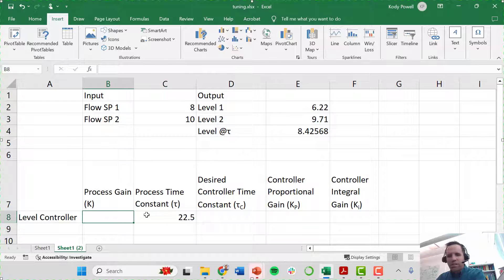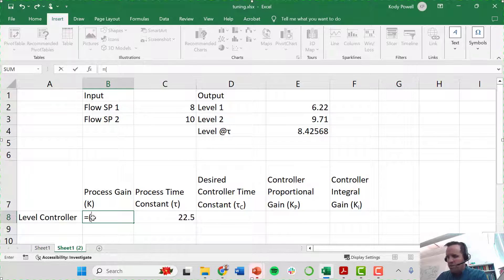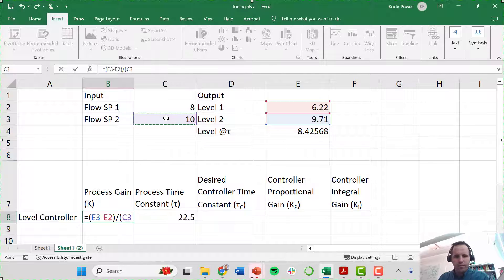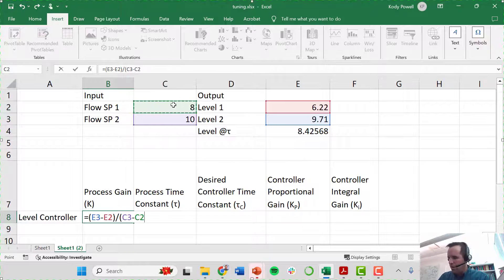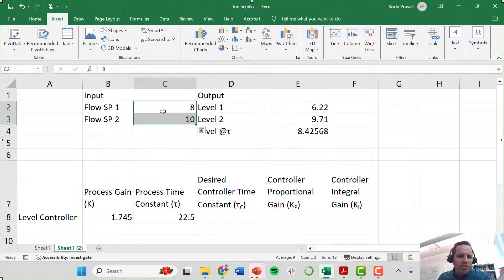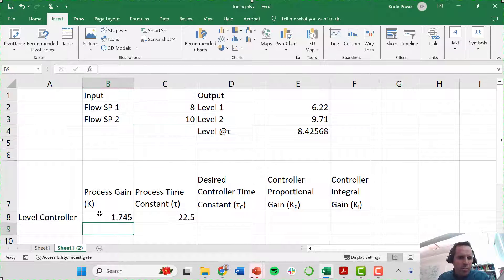My process gain I can calculate from the step test — that is the change in my output divided by the change in my input. So I have a process gain of 1.745. That means for every cubic meter per minute that I change the flow, I should expect to see roughly a change in level of about 1.745 meters.